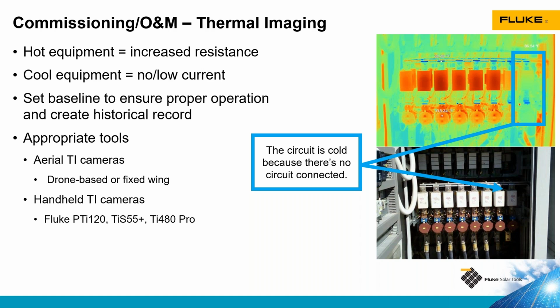There are many tools we can use for thermal imaging. As I mentioned, drone-based thermal imaging is really common in large-scale solar arrays. Fluke has a wide range of thermal cameras from the small PTI 120 pocket camera, which is about the size of a cell phone, up to the mid-range and even high-end thermal cameras like the TI 480 Pro. As you move up in the product line, the resolution that the cameras are able to provide are much greater, and the higher the resolution is, the further away from the equipment you can be and still get good quality images. So you can be outside of the electrical hazard zone and still get a good thermal image.